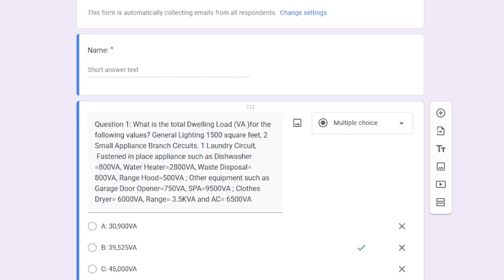I think you're right. You're close to it. Remember you changed it so the answers are different. They would say 39,525, but because you changed it from 3.5 kVA or from 10,000 to 3.5 kVA, it changes it. And with the 3.5, that's multiplied by 0.8. You still got 39,450.